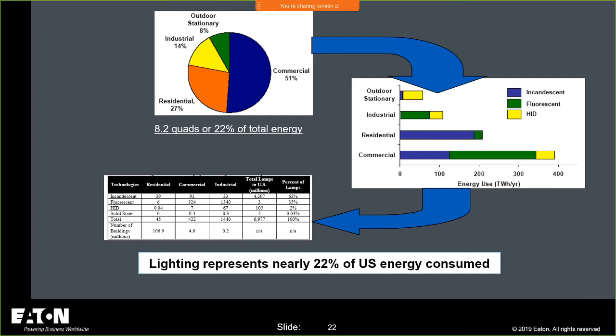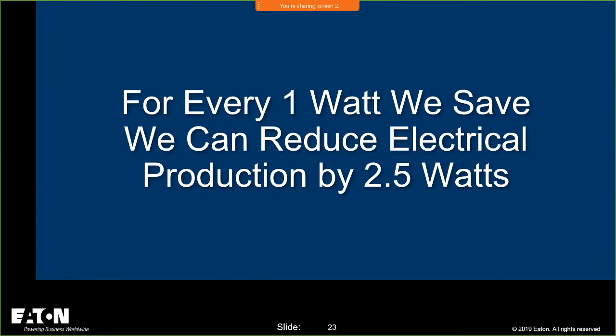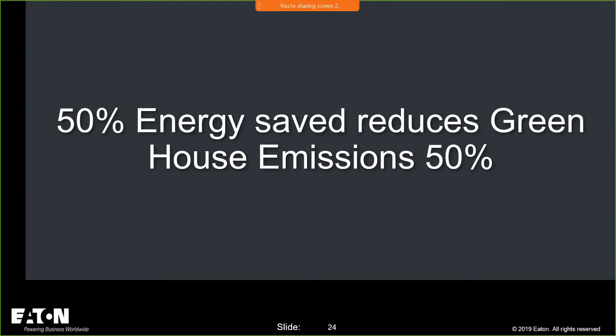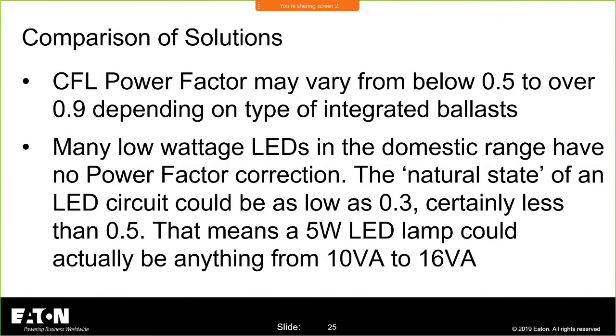And that's important, and the reason is that we talked a little bit about power factor. Yeah, I did. We talked about VA versus watts. The energy codes love to talk about watts per square foot, but we don't use watts per square foot when we size equipment. We know that if we can save 1 watt, we reduce electrical production by 2.5 watts, and energy saved reduces greenhouse emissions. So there's an energy usage play, and there's emissions, green, sustainability. That's the word I was looking for, sustainability.